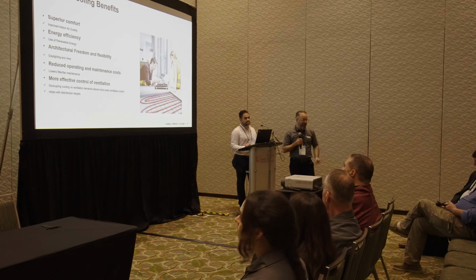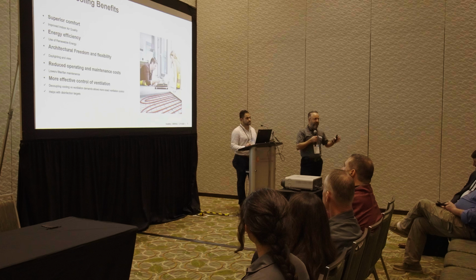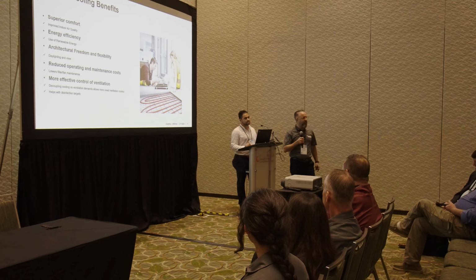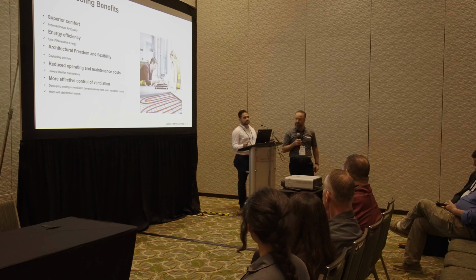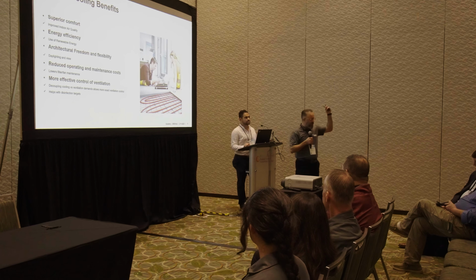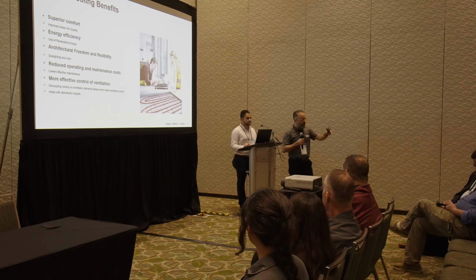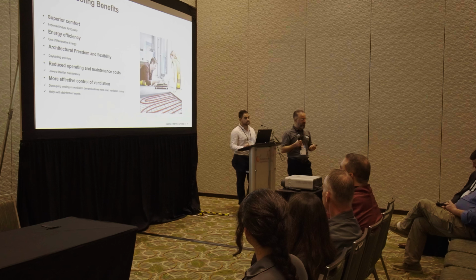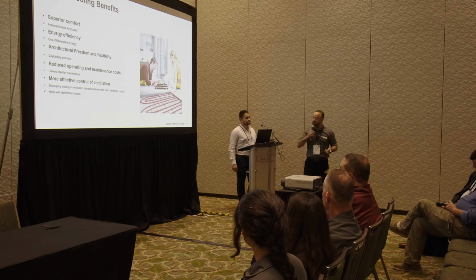Also, last but not the least, you have very good and effective control of your ventilation. I've seen some cases where they have air handling units over the top of the building, for example, a commercial building. When there is a cooling demand, that kicks in. But how about fresh ventilation? When you're talking about a hybrid system, the good thing is you can decouple these two. So radiant cooling addresses your cooling demands, but you have constant ventilation going on with your air system. In that case, your occupants, like students in the room, always feel fresh, and they enjoy that decoupling topic that I was talking about.